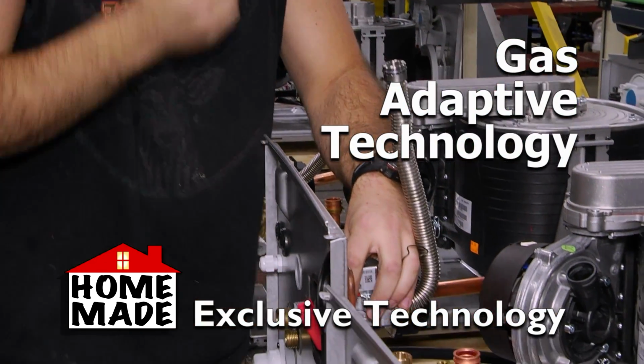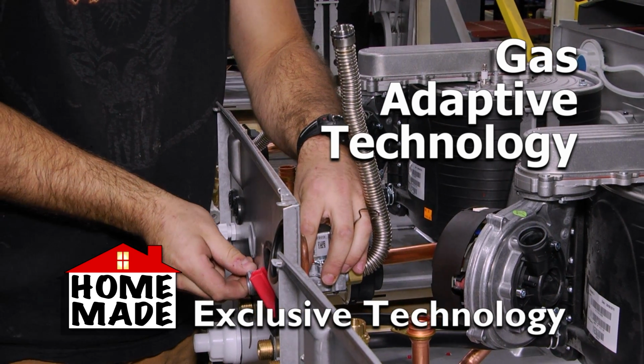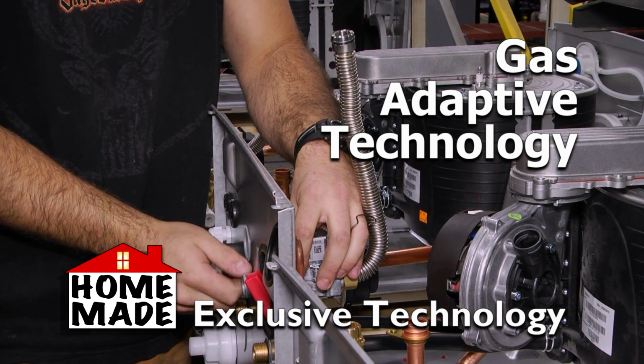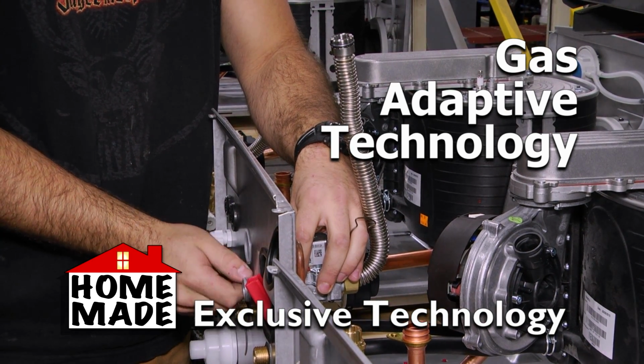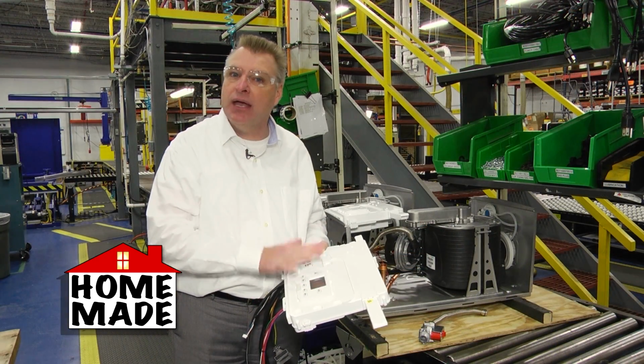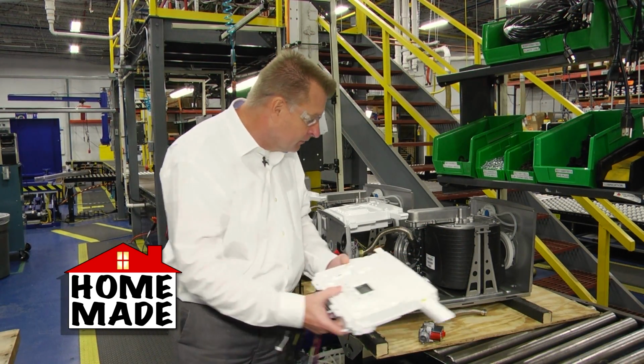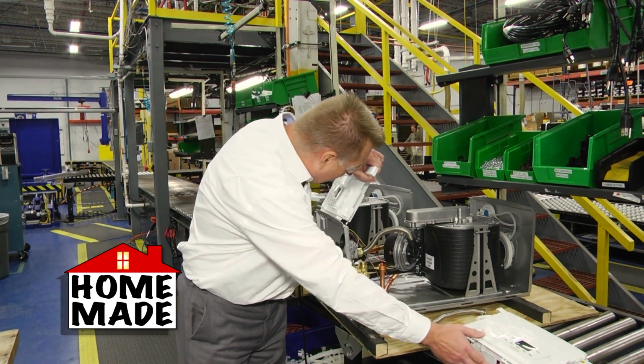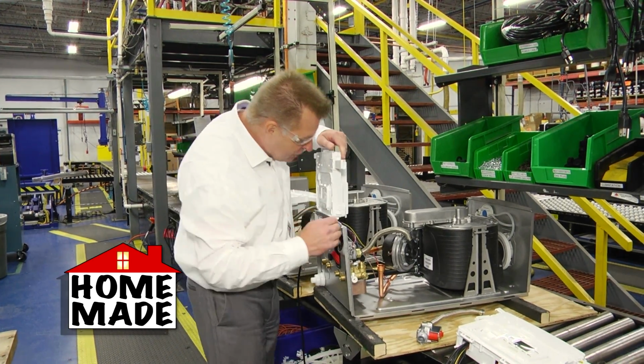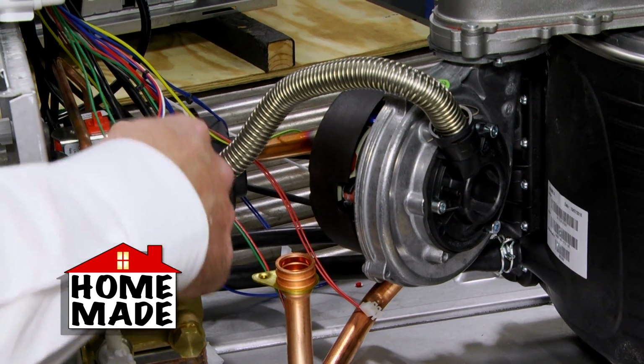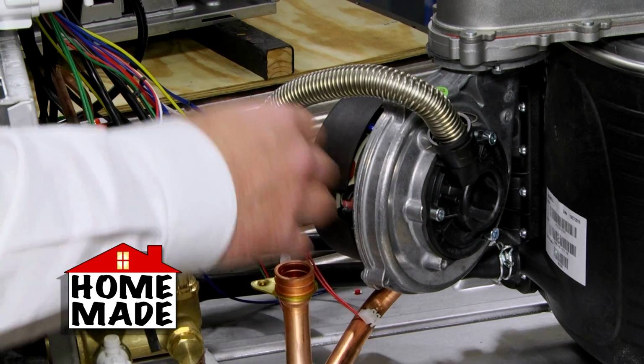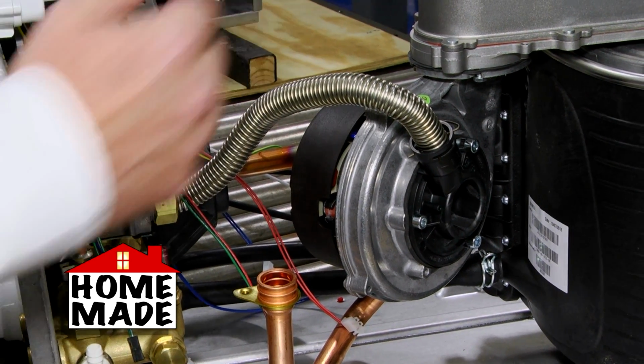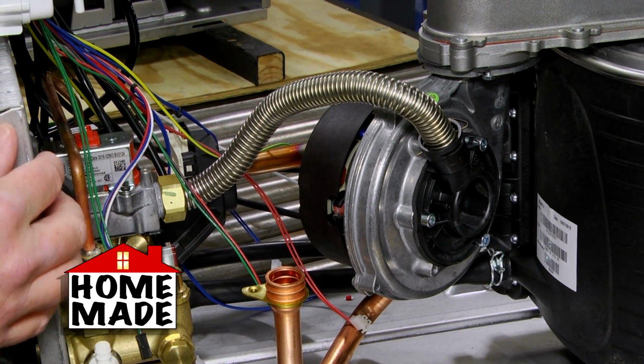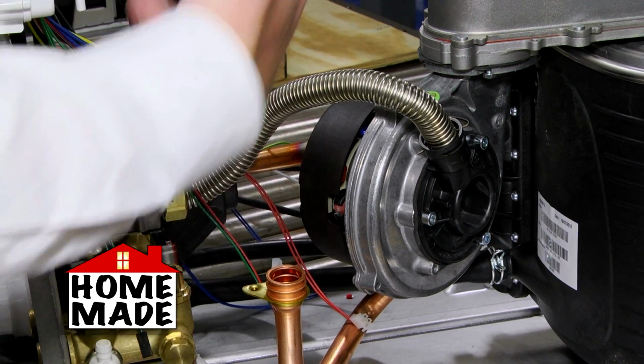Very important. Most boilers today, you pretty much have to make adjustments to the boiler based on the type of gas you're using for that boiler. This is one of the only boilers in the U.S. market that has this technology. As you can see, the gas valve, as we talked about in the previous station, here's your gas valve. Gas is coming through into the blower unit, as we discussed earlier, where it mixes with the air to cause that gas-air mixture going into the heat exchanger.